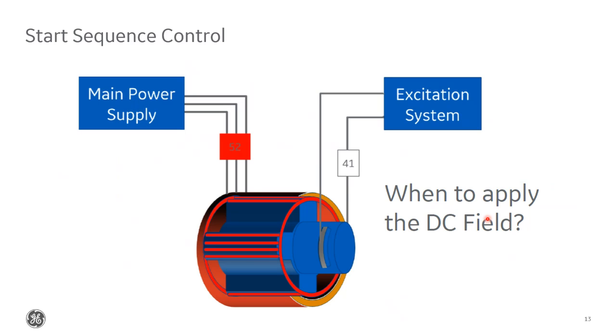Diving into a little bit more detail, let's first take a look at what's involved in start sequence control. Again, like I mentioned, one of the main functions that's required of a synchronous motor controller is the start sequence control. This function is what monitors the speed or slip and decides exactly when to apply the DC field to achieve synchronization.